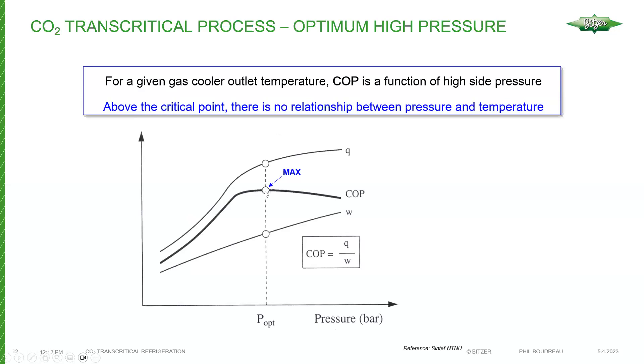Here's a fundamental point about transcritical systems: for every gas cooler outlet temperature — which depends on ambient temperature — your coefficient of performance is going to be a function of high-side pressure. The controls on the high side are always trying to optimize for the highest coefficient of performance. The highest COP isn't always achieved at a lower or higher pressure — it depends. And I'll explain that further.